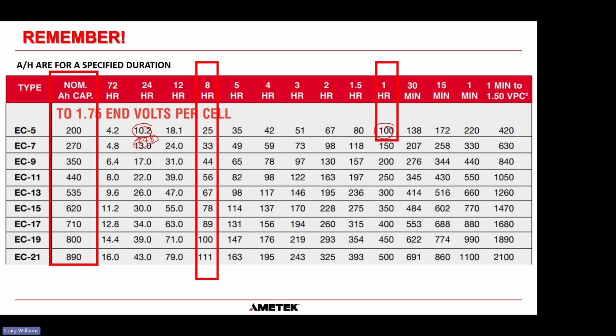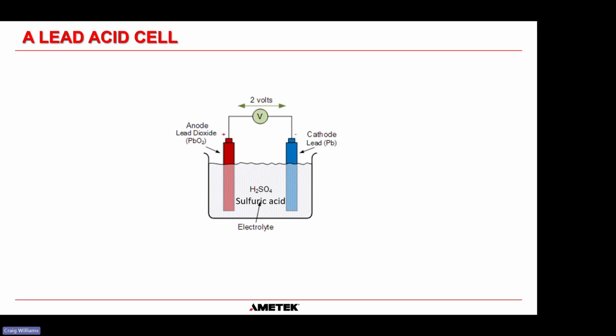So you do have to pay attention to the specifications from the battery manufacturer, and when it says what the nominal ampere hour capacity is, you have to know what C rating that is. For this cell, the C rating is 8 hours. So what it should say is for the EC5 it's a 200 ampere hour battery at the C8 rating. In other words, you will get 25 amps per hour for 8 hours. Hopefully that explains that.